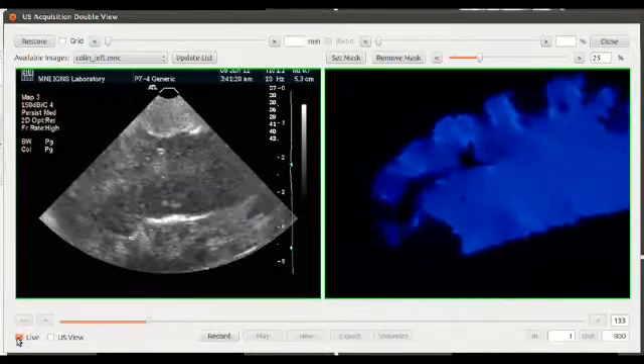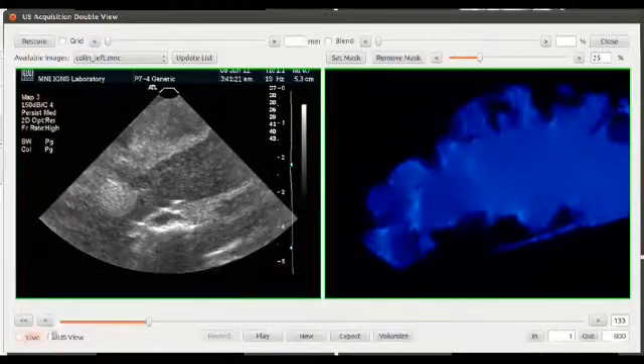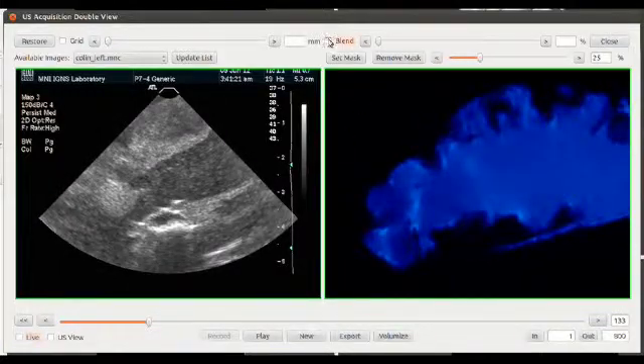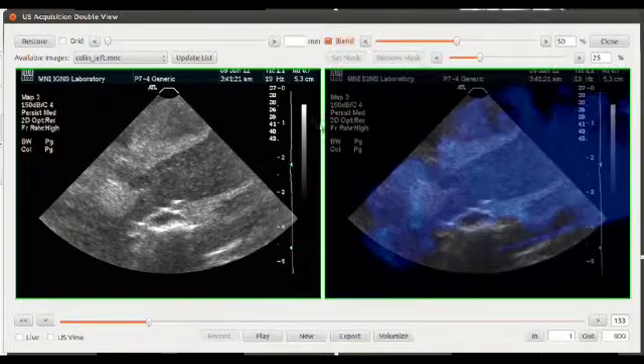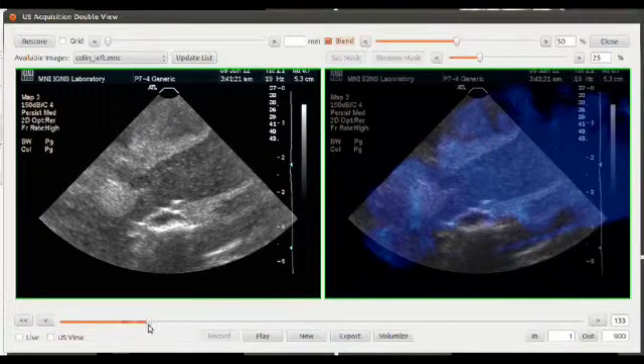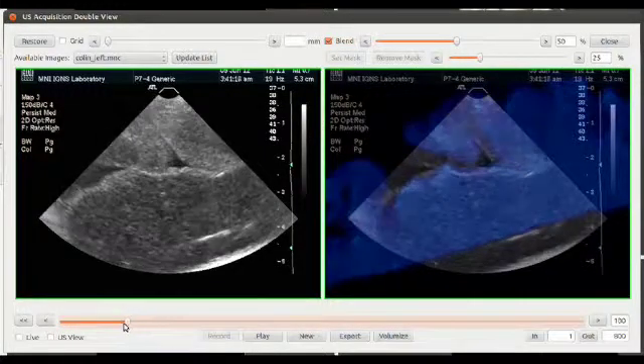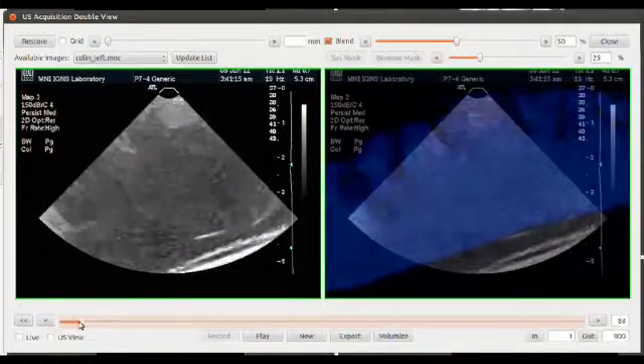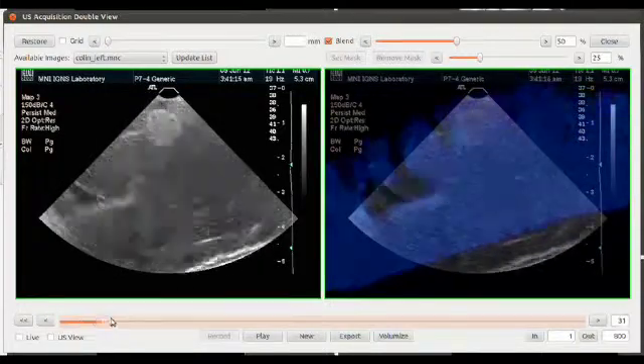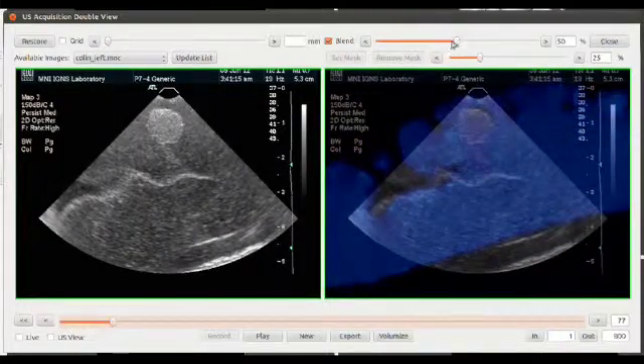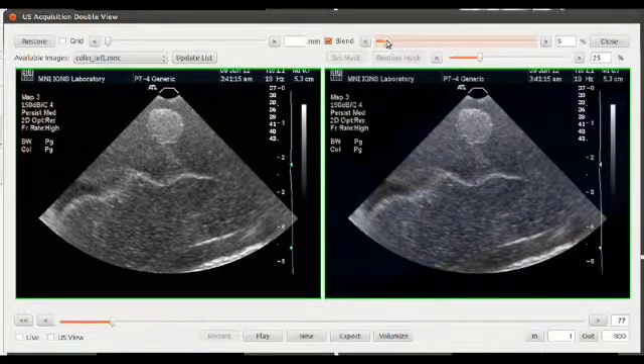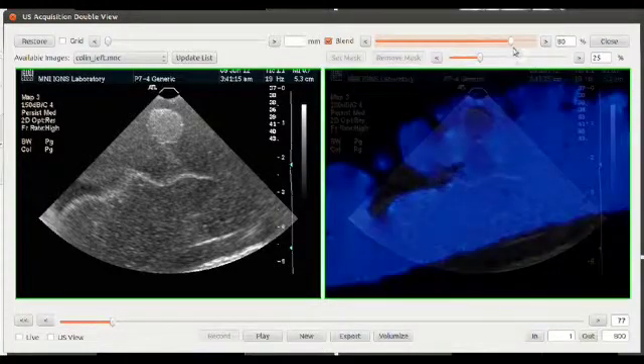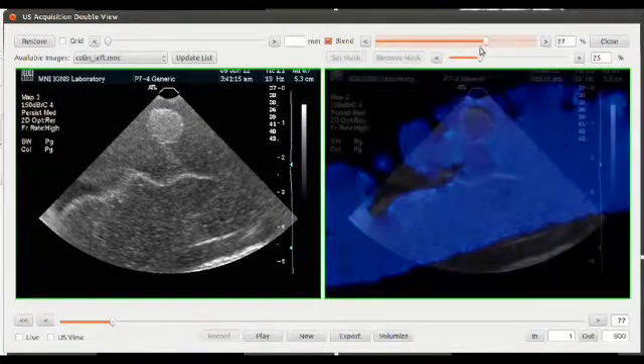Once the surgeon has finished acquiring images, they are able to replay through the acquisition as well as blend the ultrasound with the preoperative images. This blending allows for detection of areas where the patient image registration has been compromised and is no longer acceptable as an accurate means of neuronavigation.